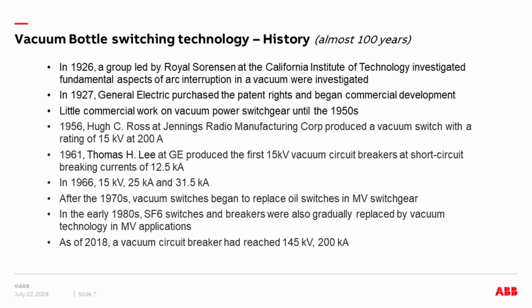So in addition to the elbows, rubber molded products, I want to talk about vacuum switching, because vacuum bottles inside molded rubber is how our switchgear works in the solid dielectric switchgear. So vacuum bottle history, you can see goes back almost 100 years to Caltech. GE bought the patent rights, but really nothing much happened for a number of decades, probably because of the Depression and then wars. But it was in the 50s when we started to see product at the medium voltage level that could actually switch and be an effective solution.